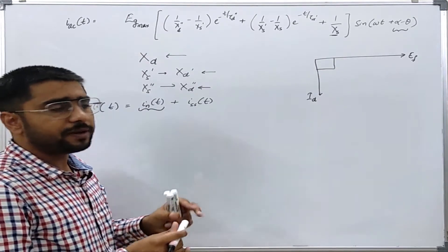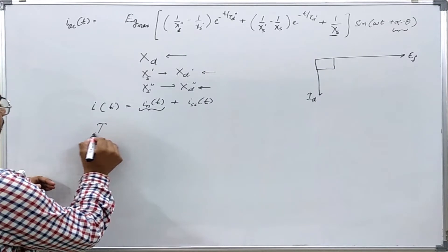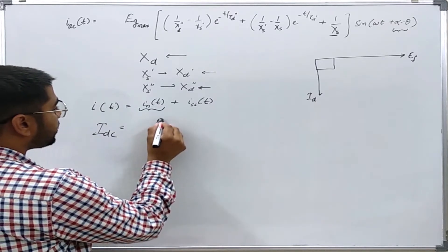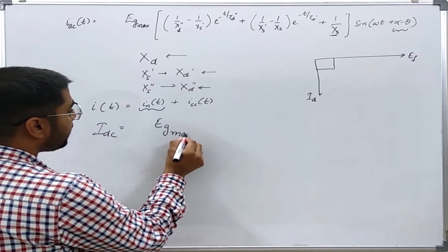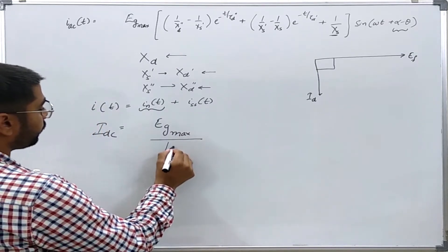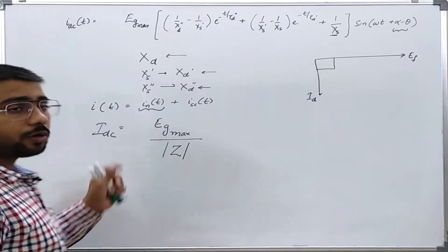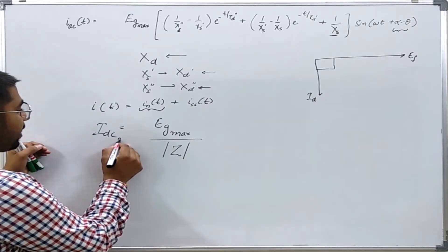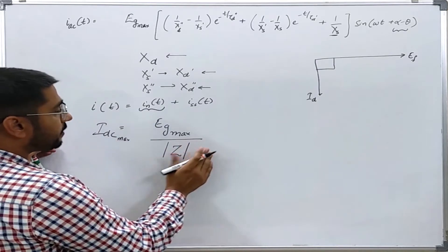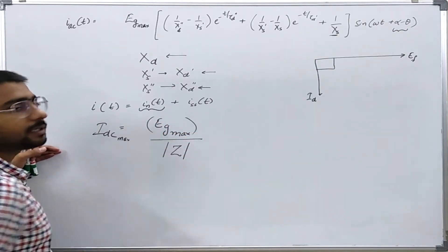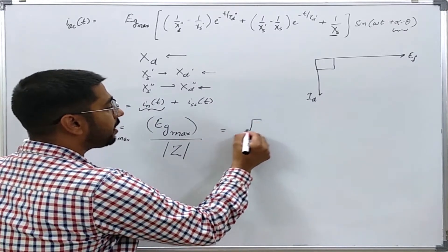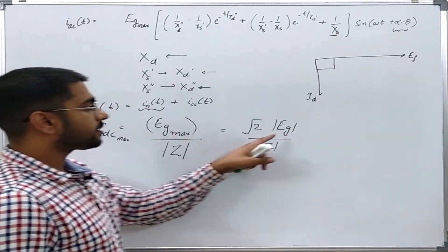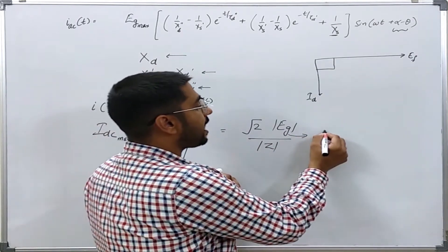We have seen in one of the previous lectures that this DC decaying part can have a value equal to the maximum value of the symmetrical part. This maximum value can go up to that peak value, and if I want to show only the RMS equivalent, I will write it as root 2 times IAC, where this symbol represents that we are dealing with RMS values. As I already mentioned at the start of this course, we will usually use RMS whenever we are dealing with phasors.